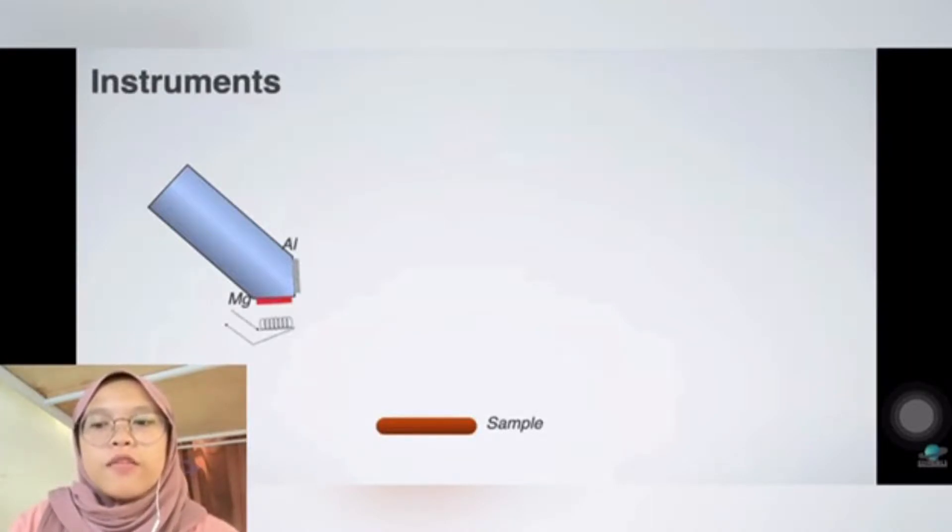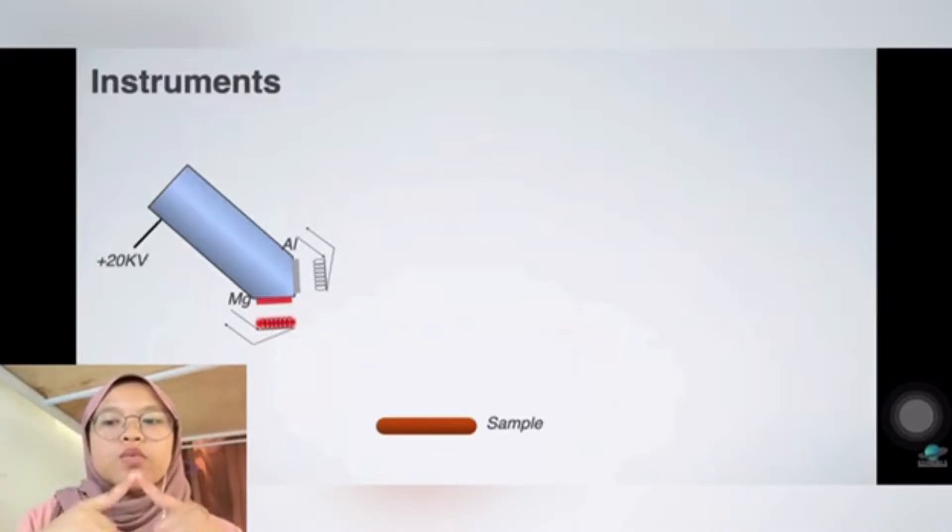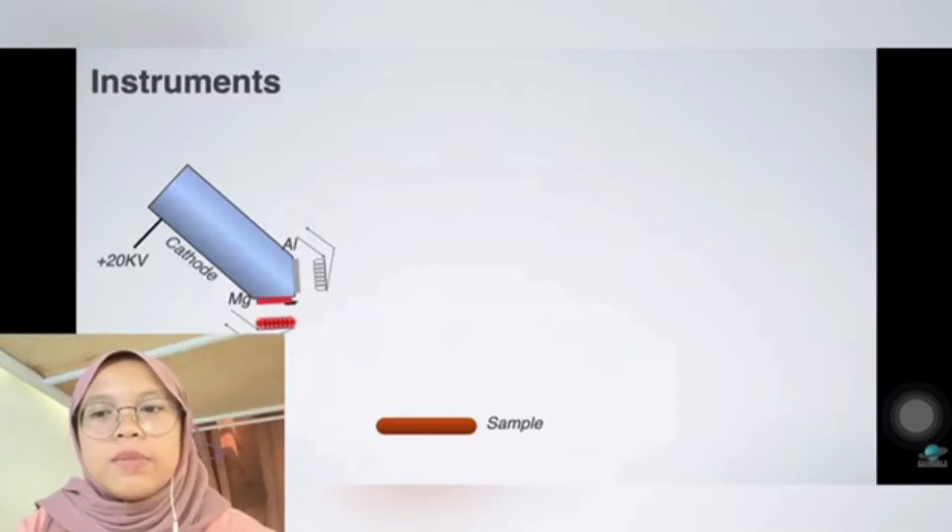There are two types of X-ray sources that are very common which are magnesium K-alpha and aluminum K-alpha. Only one source can emit both radiations, which is the X-ray source that is made of a metal tube. At the end of the tip, it has two surfaces which, one side is coated with magnesium and another side is coated with aluminum.